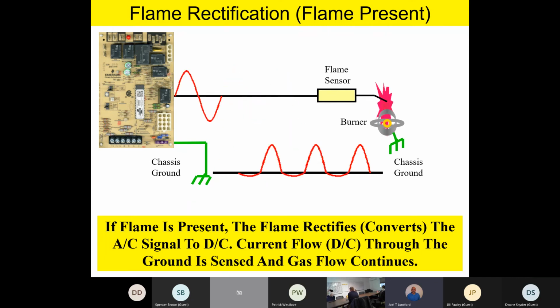pulsating DC voltage. It then takes that pulsating DC voltage, passes it through the flame and the burner, and puts that DC voltage on the ground plane. This is why it's so important that we have a really good solid ground on our furnaces, and the flame sensor has to be clean. Now we recommend cleaning that flame sensor with steel wool. I like to use stainless steel wool. Do not use sandpaper because you can leave little pieces of sand on there. So don't use sandpaper, but use something like steel wool or Scotch-Brite to clean that flame sensor. That AC voltage has to have a nice clean path to go through the flame to chassis ground.